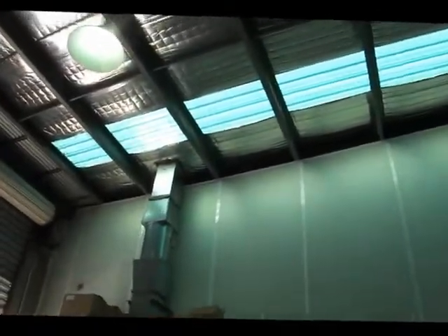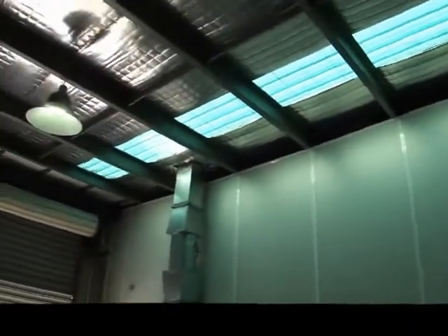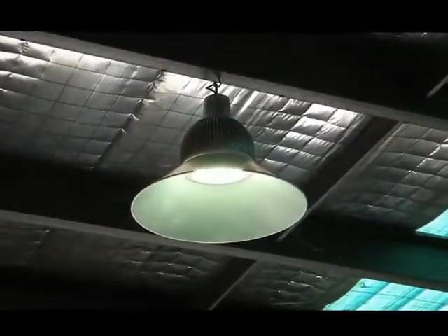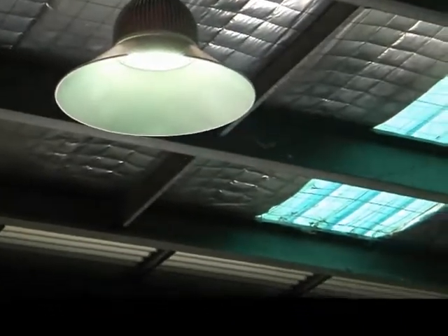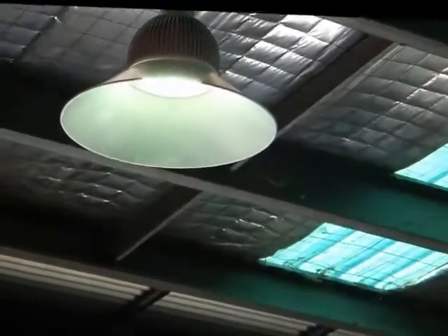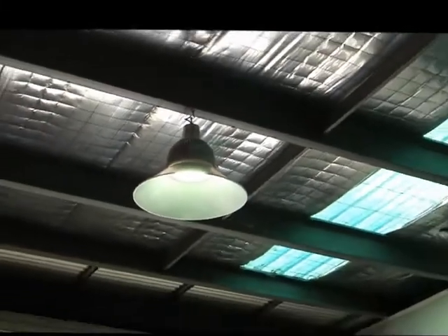The reflector actually has a special heat paste to dissipate the power from the housing to the reflector. So not only does the reflector spread the light, but it also performs the function of helping to cool the LED housing. This LED light is guaranteed for 3 years and has a life expectancy of the LED lights plus the driver. Don't forget that the driver is important, of 60,000 hours.